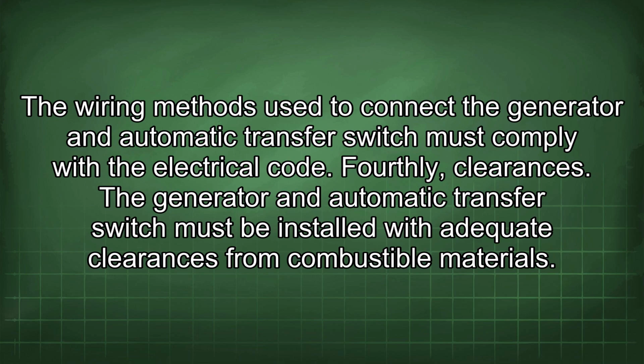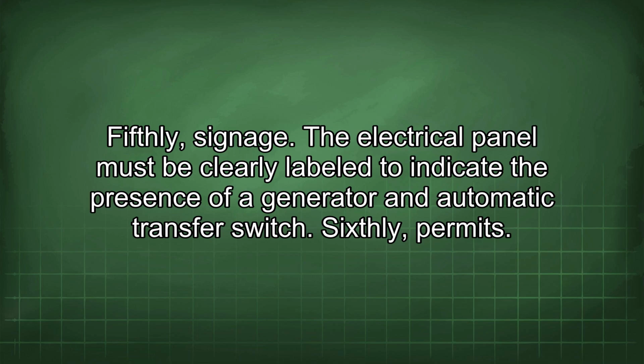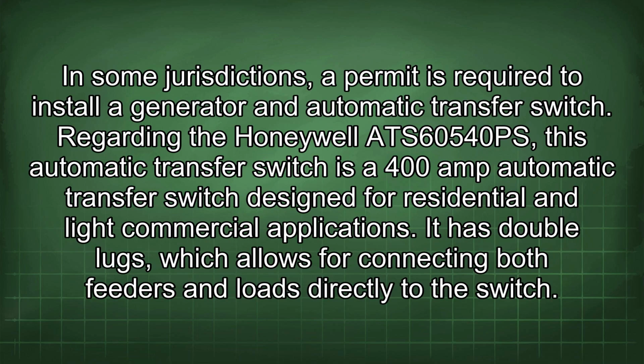The wiring methods used to connect the generator and automatic transfer switch must comply with the electrical code. Fourthly, clearances. The generator and automatic transfer switch must be installed with adequate clearances from combustible materials. Fifthly, signage. The electrical panel must be clearly labeled to indicate the presence of a generator and automatic transfer switch. Sixthly, permits. In some jurisdictions, a permit is required to install a generator and automatic transfer switch.